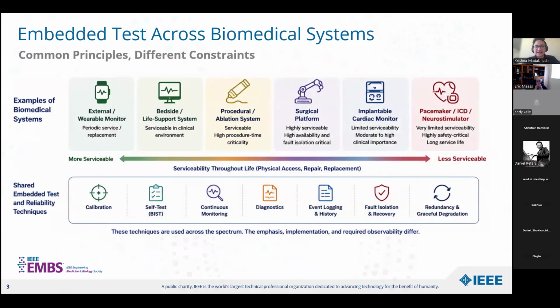The same basic test techniques appear across all the biomedical systems I'm showing here. For example, the wearable monitor, the bedside system, a surgical platform, and the implantable devices may all use the same checks: calibration, reference monitoring, current measurements, fault logging, or diagnostic signatures. So the techniques may be similar, but what changes is how critical the function is, how quickly a problem must be detected, and how easily the system can be accessed or serviced. A wearable monitor, for example, may be relatively easy to replace, while a bedside system may be regularly inspected, maintained, and calibrated. But even those systems have embedded health monitors that can reveal the problem between these scheduled service intervals. And coming to critical systems like surgical platforms, for example, they also might be very serviceable and may include extensive diagnostics.